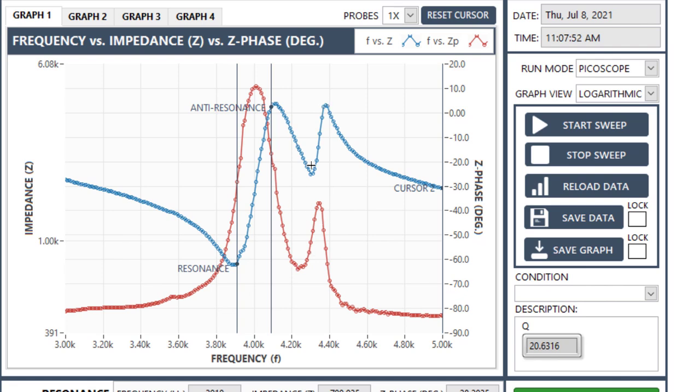So it's important to note that this occurs, and also save the data so you can look for a trend. If you look at the red, the phase, it also shows a very significant deviation from just going from 90 degrees back to negative 90 approximately.